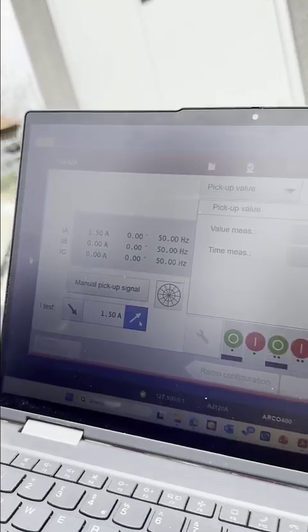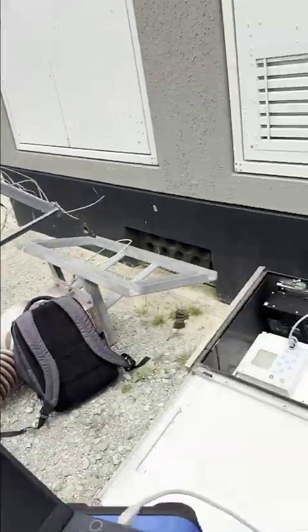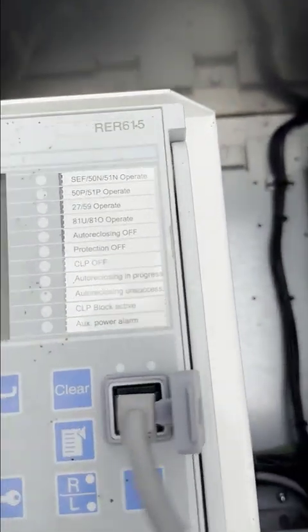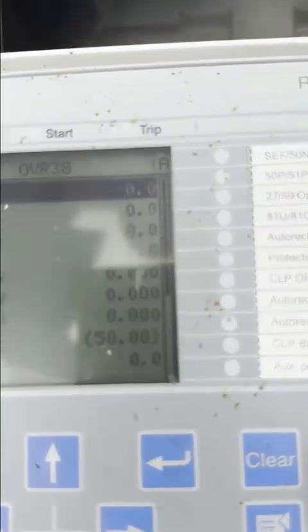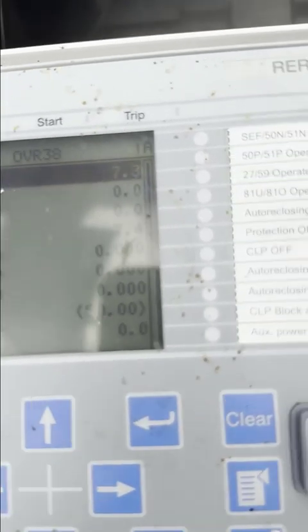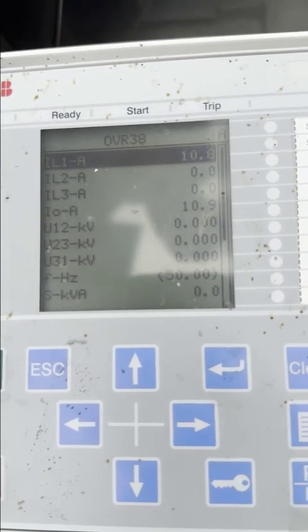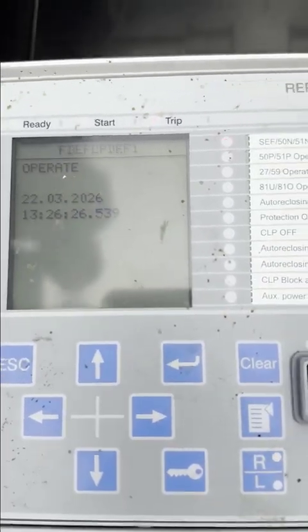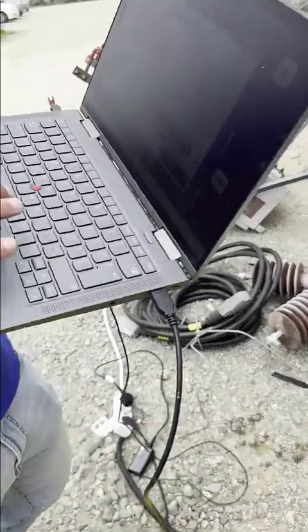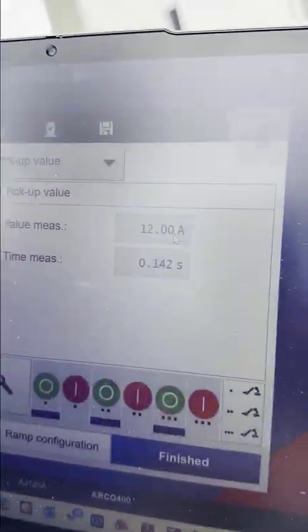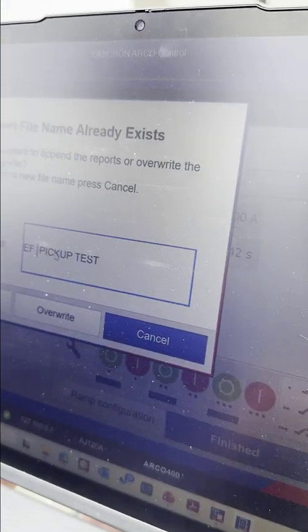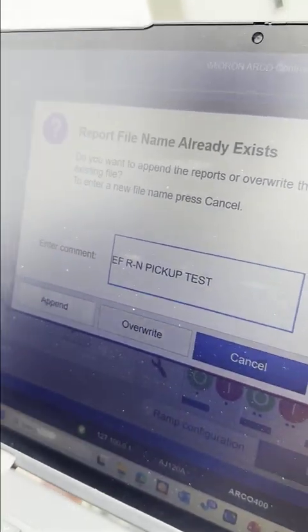So now everything is reset. You can see the relay itself. We are expecting 0.02, which equals 12 ampere. Now it's 7, 7.5, 10.5, 11, 11.5. Now it's 12, which means the start of the earth fault. You can see from here also the pickup value is 12 ampere. You can select to save it. You can change the name only to be earth fault R-N. Then you can append.